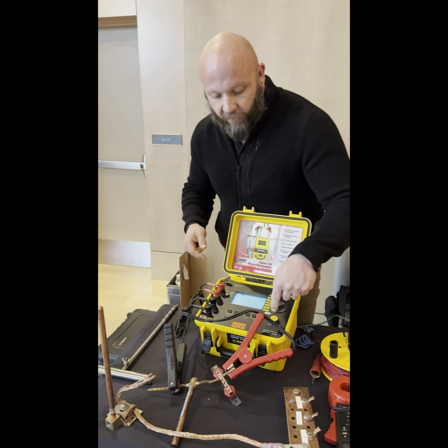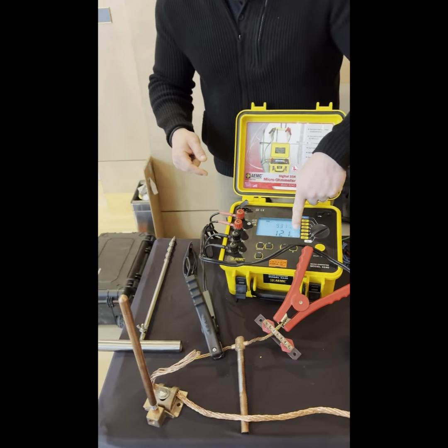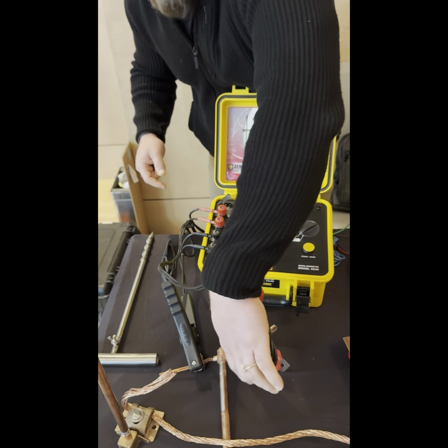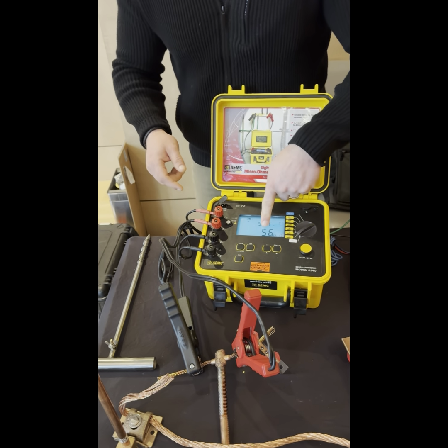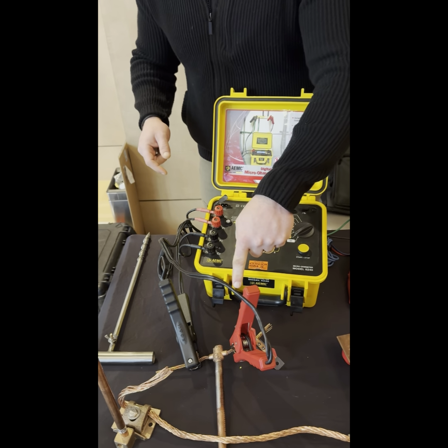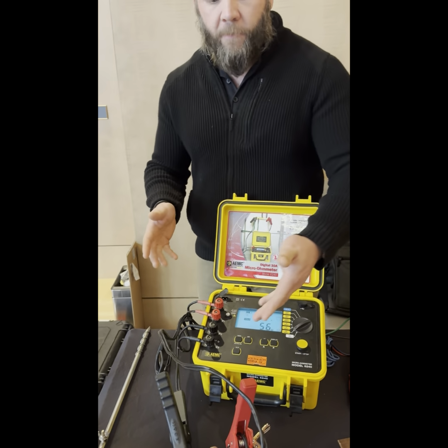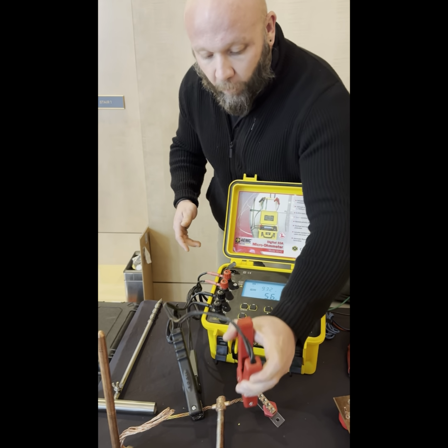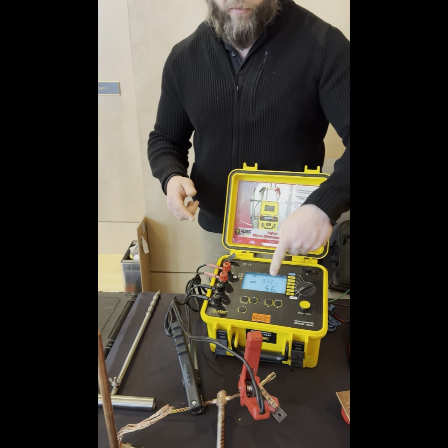But I'm going to go ahead and press the start button. You can see this red one's on the other side of this bus here, and I get 121 micro ohms. But if I move this closer, I'm still testing the same bond, the same weld. You can see now I get half that resistance. And by moving it, you may have thought if I did this 5, 10, 15 times, this one was bad, right? Because the lead was placed over here. But in reality, this bond is probably just fine due to its result.